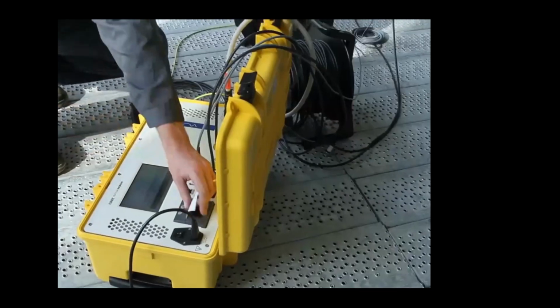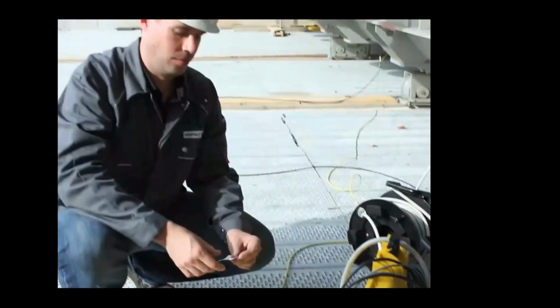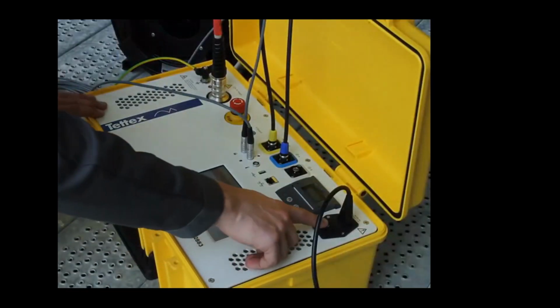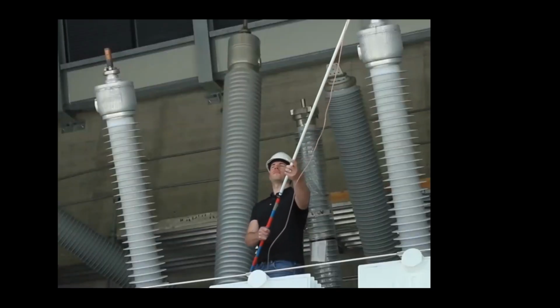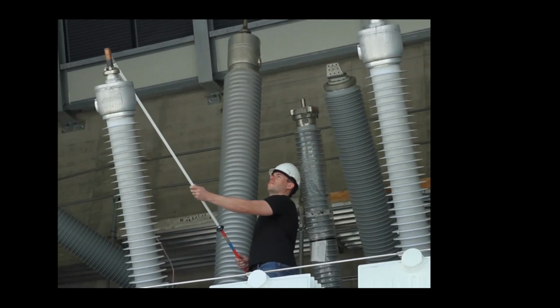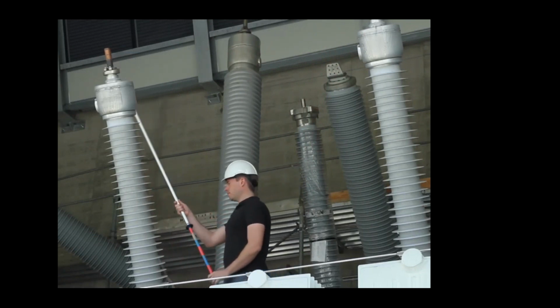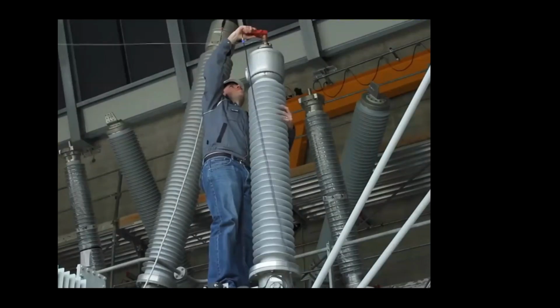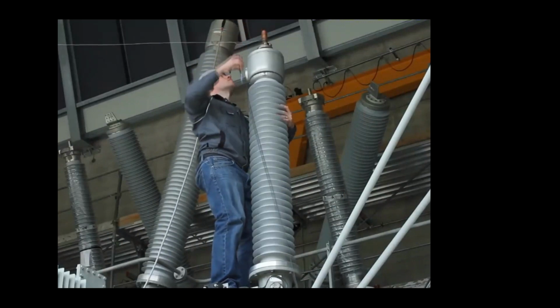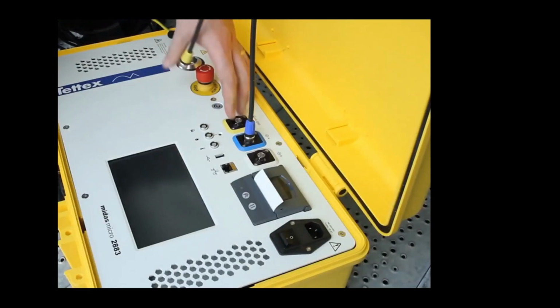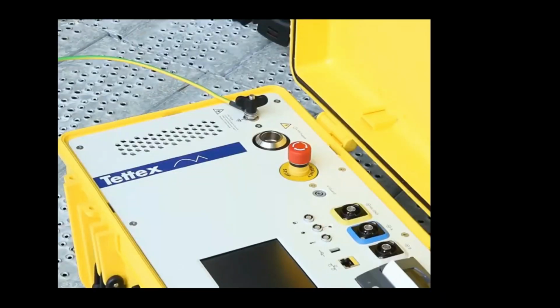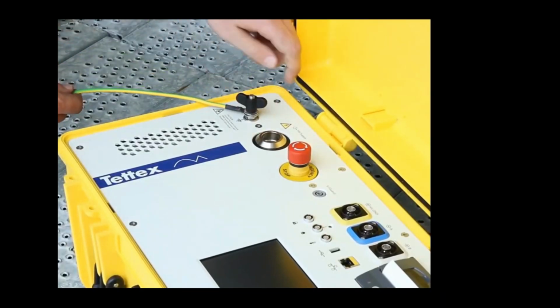Once the necessary information has been recorded, you can end the test by powering the system off. For safety, use a grounding stick to discharge the device under test prior to removing connections. Disconnect all test leads from the DUT before disconnecting from the MIDAS Micro. The green and yellow safety ground cables should be the last leads disconnected from the MIDAS Micro.